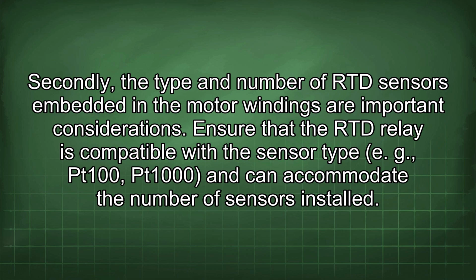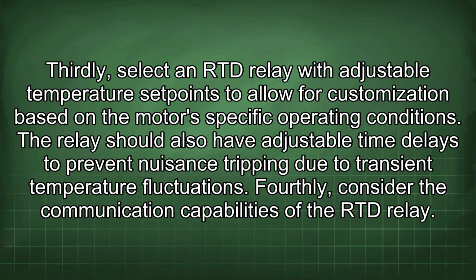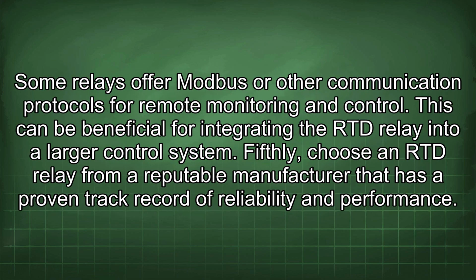number of sensors installed. Thirdly, select an RTD relay with adjustable temperature set points to allow for customization based on the motor's specific operating conditions. The relay should also have adjustable time delays to prevent nuisance tripping due to transient temperature fluctuations. Fourthly, consider the communication capabilities of the RTD relay. Some relays offer Modbus or other communication protocols for remote monitoring and control. This can be beneficial for integrating the RTD relay into a larger control system.